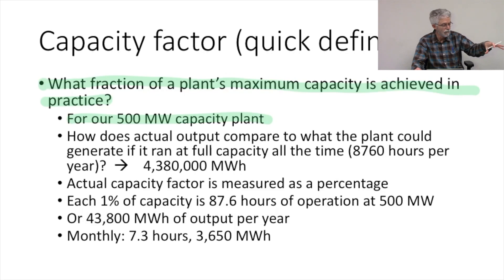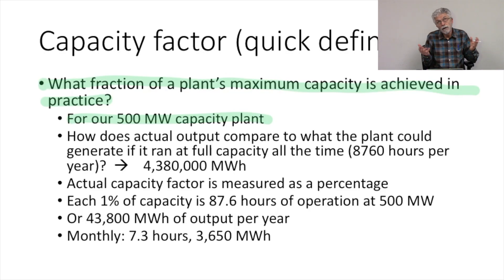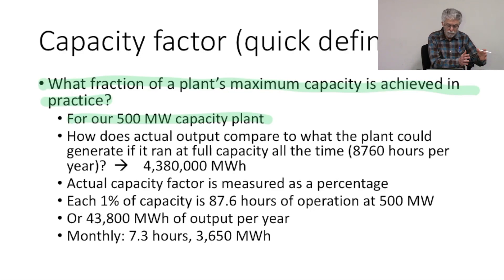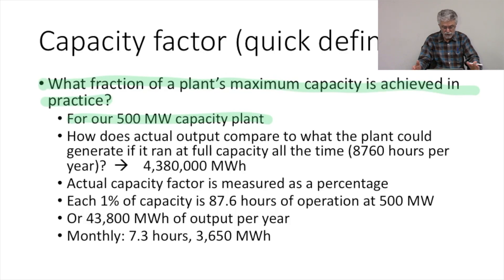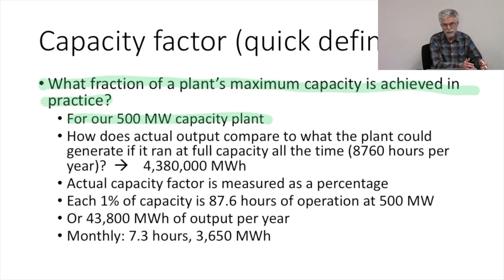The capacity factor is a measure of how what we're actually generating compares to what we could generate if the plant ran at full capacity for the entire period. Moving this down to monthly capacity: a month has about 730 hours. A 1% capacity factor in a month would have the plant running about 7.3 hours, generating about 3,600 megawatt hours. The full monthly capacity would be running at 500 megawatts for 730 hours; a 1% capacity factor has 500 megawatts running for 7.3 hours a month.